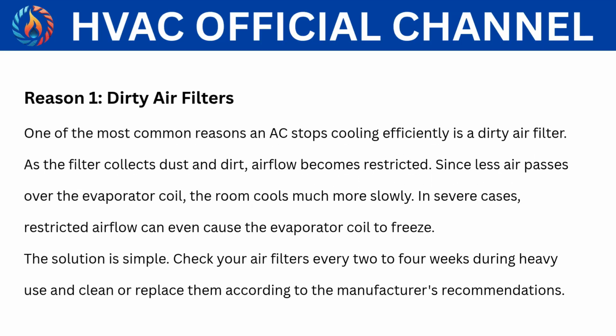Reason 1. Dirty air filters. One of the most common reasons an AC stops cooling efficiently is a dirty air filter. As the filter collects dust and dirt, airflow becomes restricted. Since less air passes over the evaporator coil, the room cools much more slowly. In severe cases, restricted airflow can even cause the evaporator coil to freeze. The solution is simple. Check your air filters every 2 to 4 weeks during heavy use and clean or replace them according to the manufacturer's recommendations.